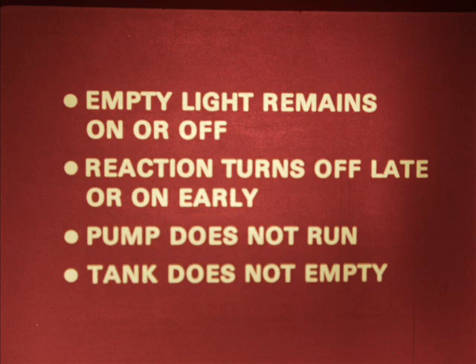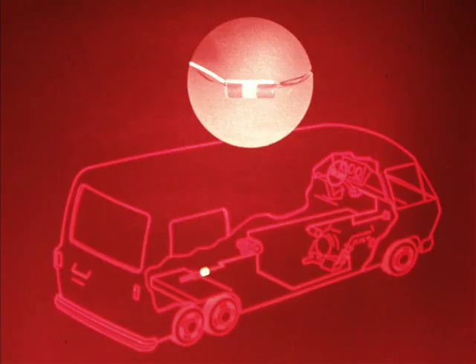The empty light remains on or off. The reaction light goes out too late or comes on too soon. The pump does not run, and the holding tank level does not go down. If the white empty light remains on or off all the time, it indicates that the level indicator is defective and needs replacing. The level indicator module is connected to the evacuation probe and affixed to the evacuation probe hose.